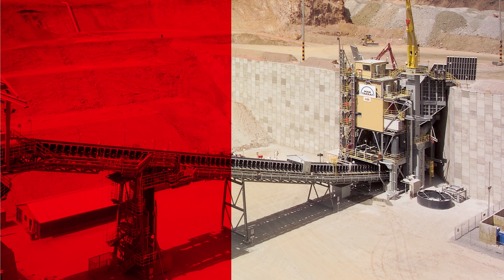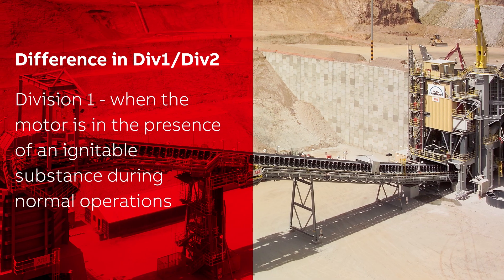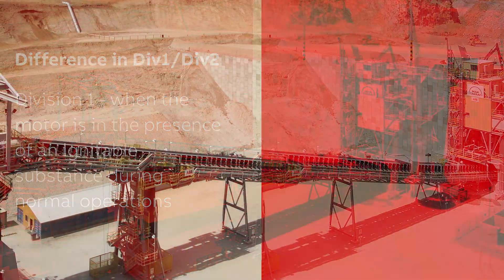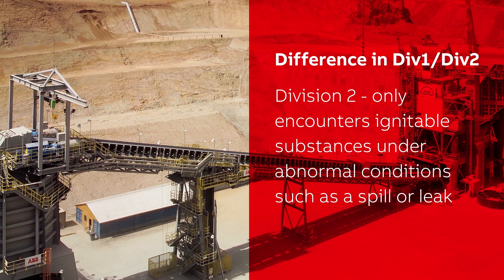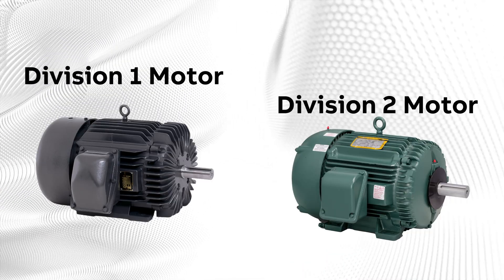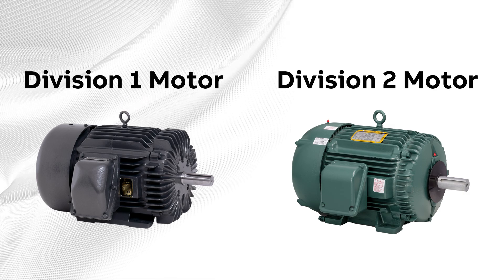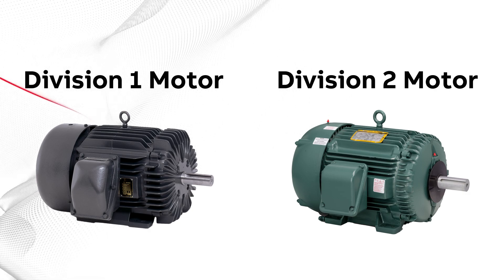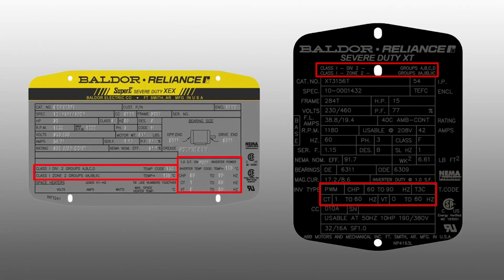In summary, we covered the difference between Division 1 and Division 2 areas — Division 1 being when the motor is in the presence of an ignitable substance during normal operations, and Division 2 being when the motor only encounters ignitable substances under abnormal conditions such as a spill or leak. We also looked at the classes and groups that define hazardous substances, and the differences in the motors: Division 1 having long flame paths, limited surface temperatures, and thicker enclosures; Division 2 having a standard enclosure, limited surface temperatures, and no sparking devices. Finally, we covered how to identify Division 1 and Division 2 motors by their nameplates.